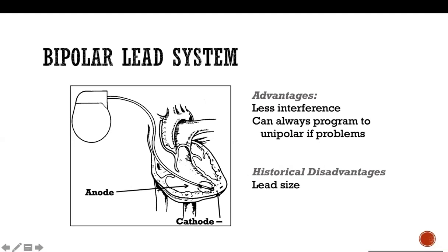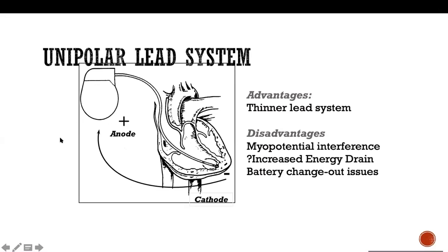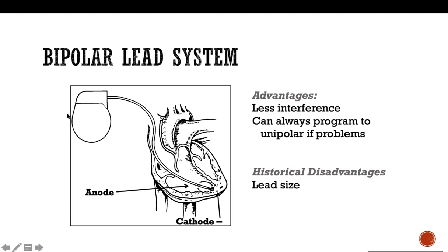For bipolar, the electricity is transmitted within a very small, focused area, which we call the tip of the lead, and proximal to the tip there is what we call the ring. Those are the electrodes that transmit the signal. So for example, if you have high electrical energy somewhere here, like a cell phone close to the device, that could interfere with the electrical signal transmitted from the device into the lead. But if you have something close here, it usually shouldn't affect the electrical signal generated from the tip to the ring. So the bipolar ones are usually more stable. They don't get affected much externally.